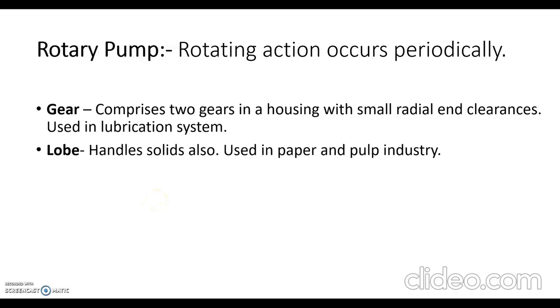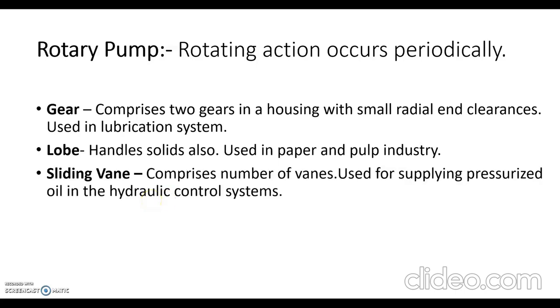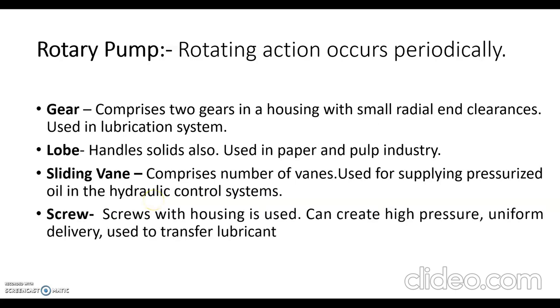Lobe pumps consist of two lobes which can handle solids. They are used in paper and pulp industry, and also in food industry. Sliding vane or vane pump comprises a number of vanes used for supplying pressurized oil in hydraulic control systems. Screw pumps with housing can create high pressure and are used to transfer lubricants.